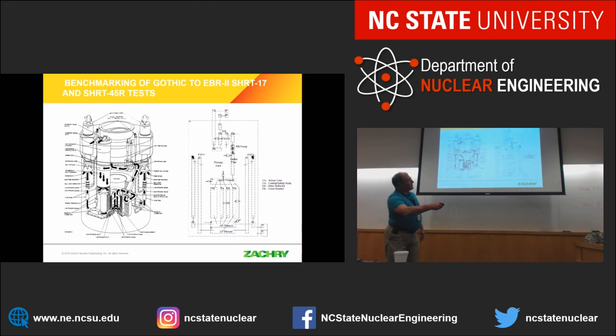The third channel was the inner reflector, and the inner reflector is mostly stainless, and an outer blanket, which are mostly spent assemblies, okay? Low power, not much reactivity left to it, but still has some residual decay heat, okay? And so, we have a pump, control volumes modeling the piping, control volumes modeling the inlet and outlet plenums, the Z pipe, a configuration to simulate the electromagnetic pump and control volumes with thermal conductors to model the heat exchangers to transfer the heat. Okay, and it all sits in a pool of sodium.